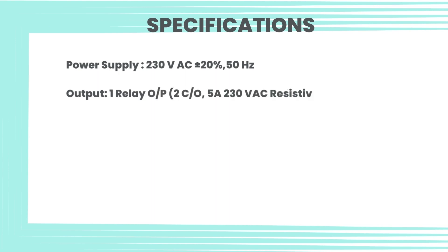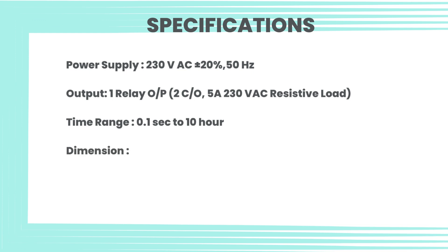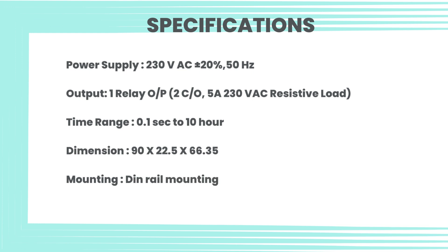Specifications — Power supply: 230 volt AC plus or minus 20 percent, 50 hertz. Output: one relay output, 2CO, 5 ampere, 230 volt AC resistive load. Time range: 0.1 seconds to 10 hours. Dimension: 90 by 22.5 by 66.35. Mounting: DIN rail mounting.